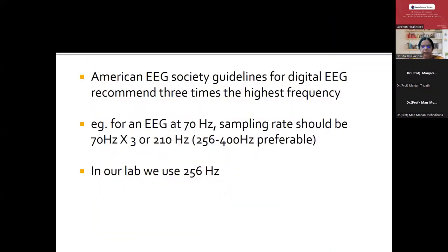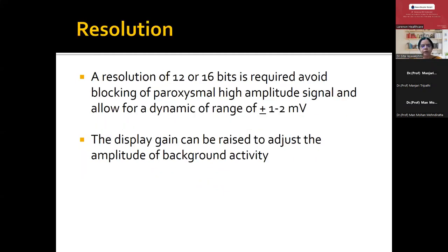The American EEG Society guidelines suggest that for an EEG recorded at 70 hertz frequency, the sampling rate should be three times the highest frequency — around 210 hertz. But in most digital machines nowadays, the sampling rate is around 256 hertz, which is reasonably good because the highest frequency we are recording is 70 hertz. But with continuous EEG recordings, the sampling rate used is very high — almost up to 1000 hertz. The resolution of the monitor should be around 12 to 16 bits to avoid blocking of paroxysmally high amplitude signals.